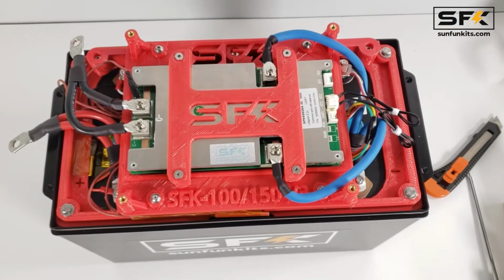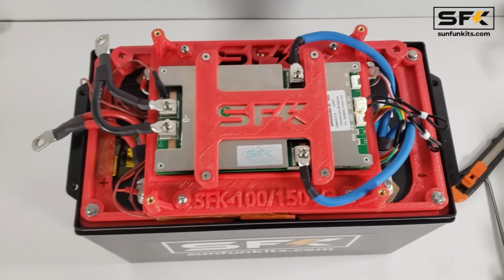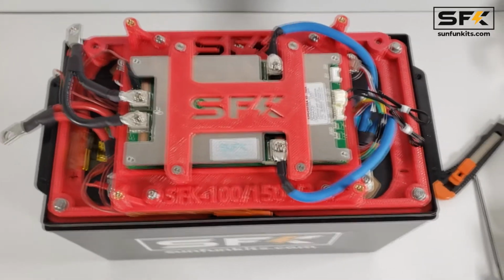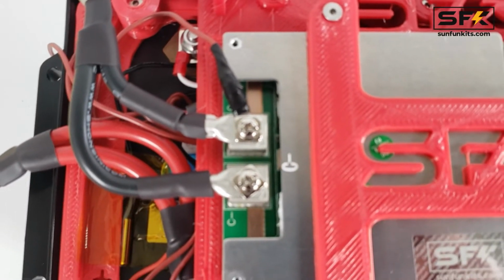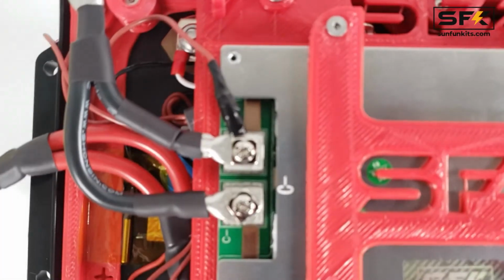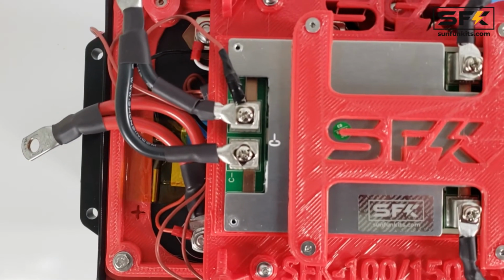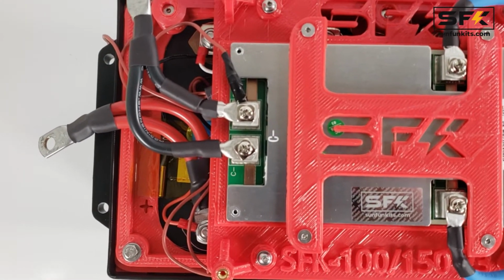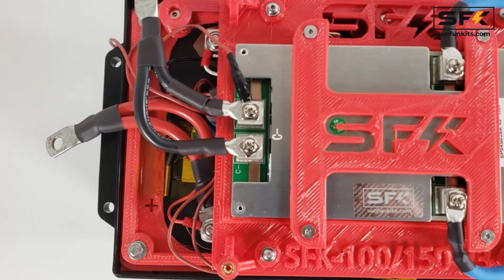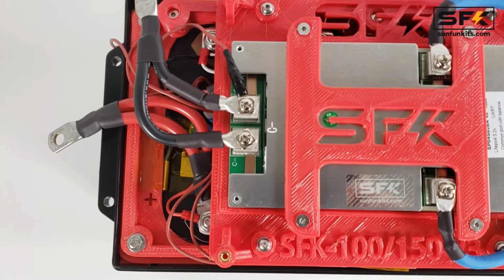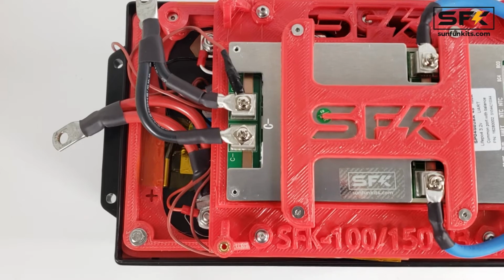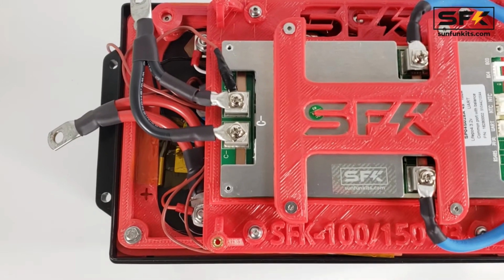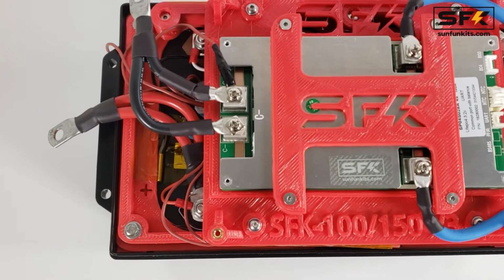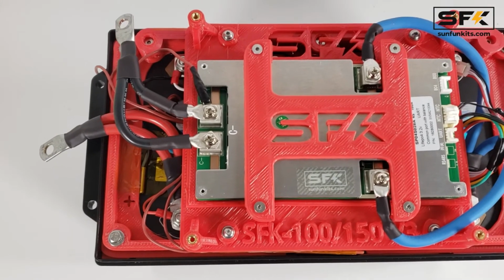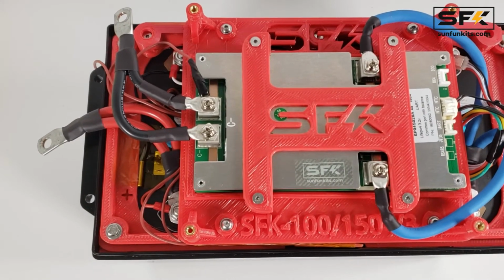Attaching wires to your BMS for the heated kit is very similar to the standard kit, with the exception that the heated port is added to the alternative side of the BMS. You can see the thermostat's negative is attached to the C-minus, or current negative, of the BMS. It's extremely important that your BMS and thermo switch are wired this way.